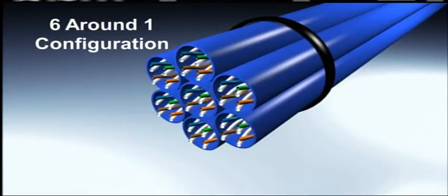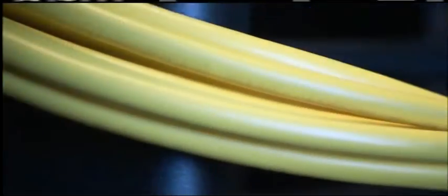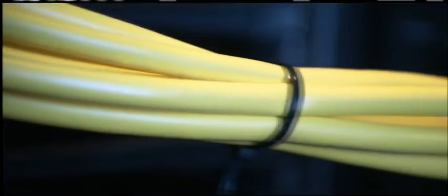This is a worst-case scenario that really tests the ability of a cable construction to limit alien crosstalk. In the Anixter lab tests, this 6Around1 bundling is done throughout a full channel, including connecting hardware.